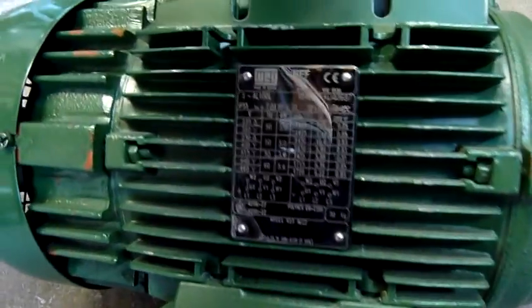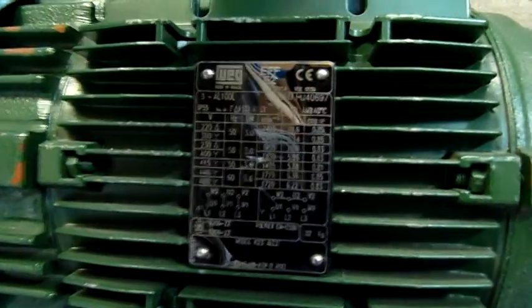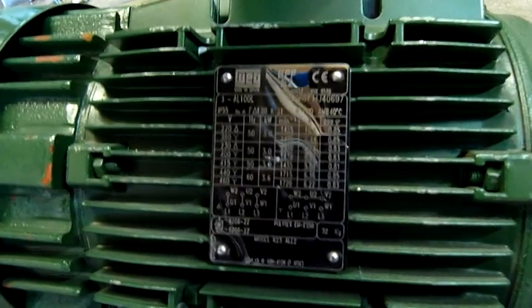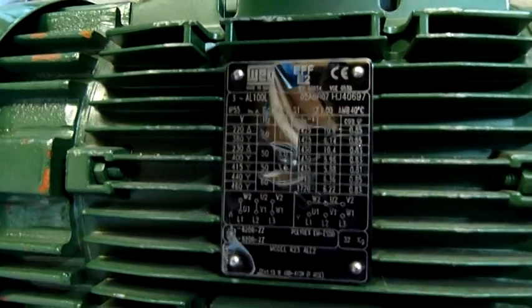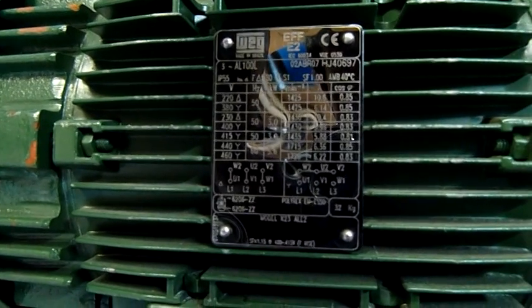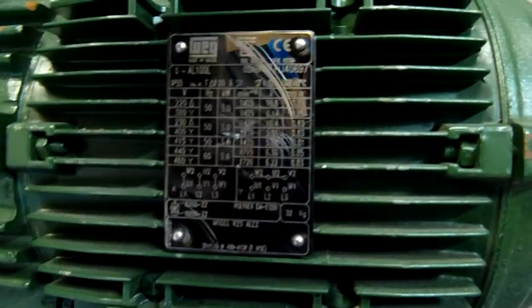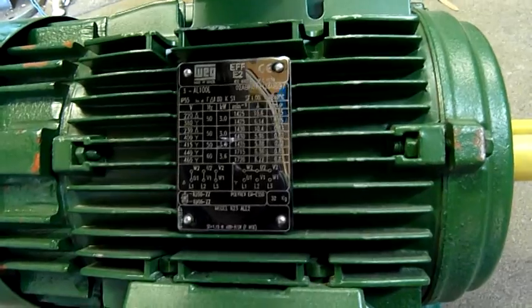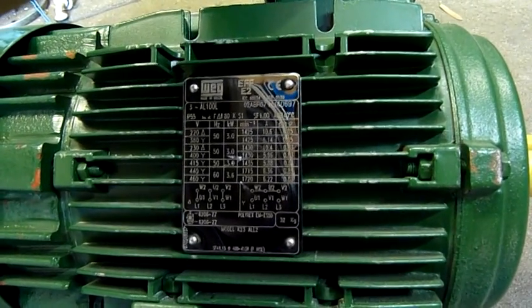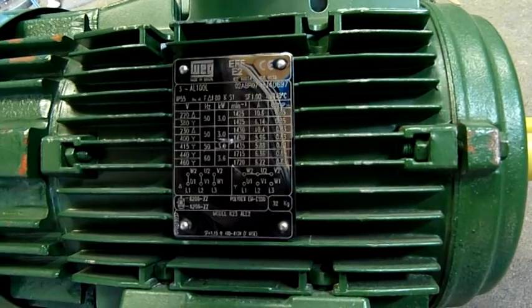It's made by WEG - I think they make them all in Brazil. As you can see: 3 kilowatts, 220 volt delta or 380 volt star, all the way up to 440 volt, 3.6 kilowatts at 60 hertz. We're only running on 50 hertz so this is only a 3 kilowatt motor, but 440 or 460 volt at 60 hertz in star will be 3.6 kilowatts.